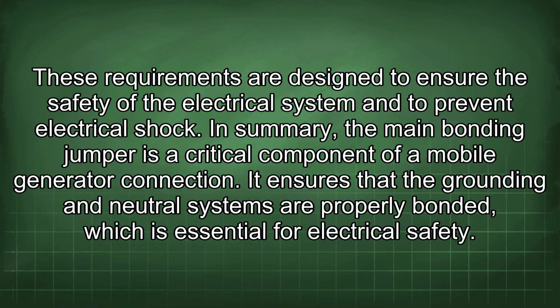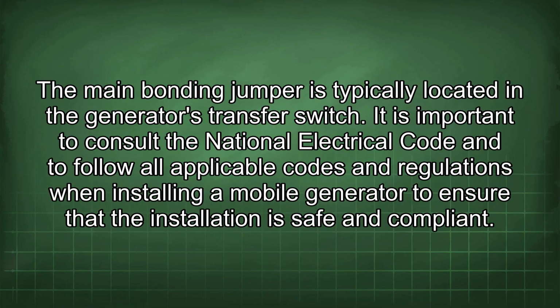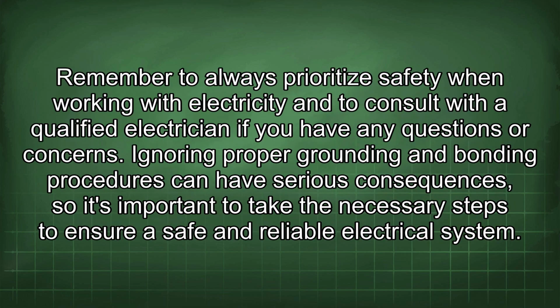In summary, the main bonding jumper is a critical component of a mobile generator connection. It ensures that the grounding and neutral systems are properly bonded, which is essential for electrical safety. The main bonding jumper is typically located in the generator's transfer switch. It is important to consult the National Electrical Code and to follow all applicable codes and regulations when installing a mobile generator to ensure that the installation is safe and compliant. Remember to always prioritize safety when working with electricity and to consult with a qualified electrician if you have any questions or concerns. Ignoring proper grounding and bonding procedures can have serious consequences, so it's important to take the necessary steps to ensure a safe and reliable electrical system.